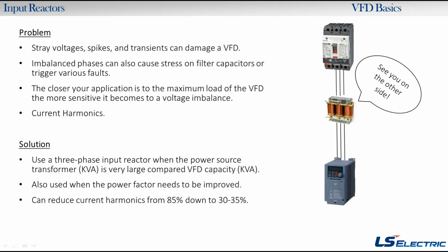Okay. Also, if you're running your VFD very heavily loaded, it's going to be more sensitive to a voltage imbalance, which could cause input phase loss issues and things like that. If you put a reactor on there, that'll help balance that out. And if you need to improve the overall power factor, an input reactor is going to help. It'll also protect the drive from those transients and spikes. So if you have dirty power, or power that's susceptible to being imbalanced, we'd recommend an input reactor. And we can also help you guys size and select those if you ever need.